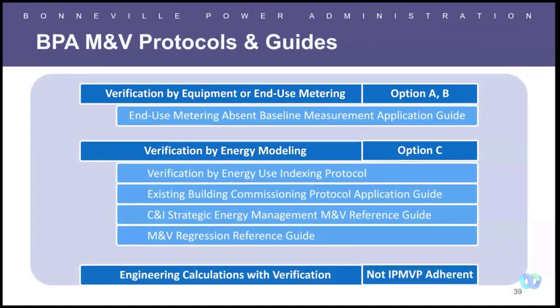If you map these to the rest of the BPA M&V portfolio, you'll see you have your verification by equipment or end-use metering, and that's either going to be an option A or an option B. This is equipment level or end-use level metering, so this is energy metering. It could be an option A where you're metering key parameters instead of the entire energy. And then you have the end-use metering absent baseline measurement application guide, which squarely fits underneath verification by end-use metering. That's if your baseline data is either not available or not applicable for some reason.